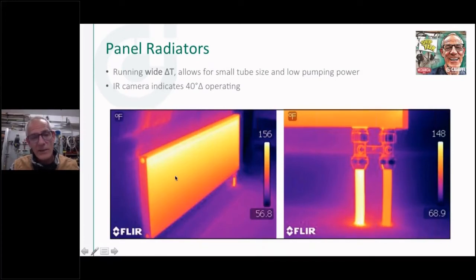The nice thing about these panel radiators, a couple things: number one, I can run them at a wide delta T, which means if I'm returning at this temperature, I'm in a great condition for my mod con boiler. I can use really small diameter tube because I'm running that wide delta T, and I don't need a lot of pumping power. I don't need a lot of flow to run that wide delta T. So my pipe size goes down, my pump size goes down, and I get down into my condensing conditions with that low supply temperature. Not quite what I'm going to get with a radiant slab perhaps, but that's a pretty nice heat emitter. You can see why most of Europe is heated with panel radiators.